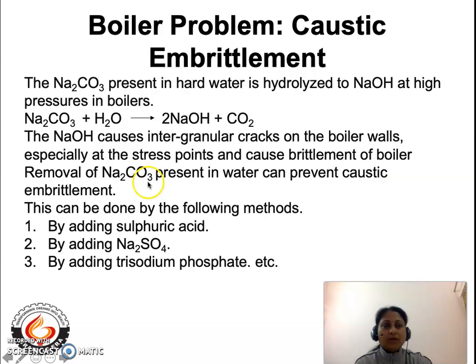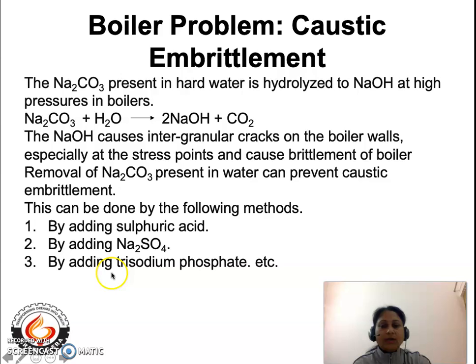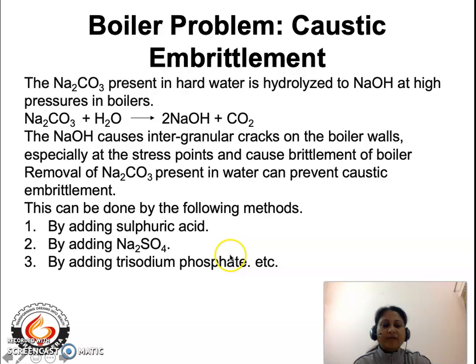Note that sodium carbonate does not cause hardness of water — hardness is caused only by calcium and magnesium salts. To prevent caustic embrittlement, sodium carbonate can be neutralized by adding sulfuric acid, sodium sulfate, or trisodium phosphate to the water. Once caustic embrittlement has started inside the boiler it is very difficult to remedy, so only preventive methods are effective.